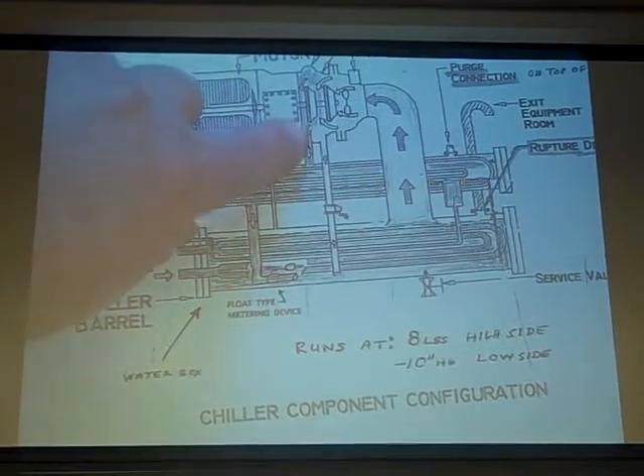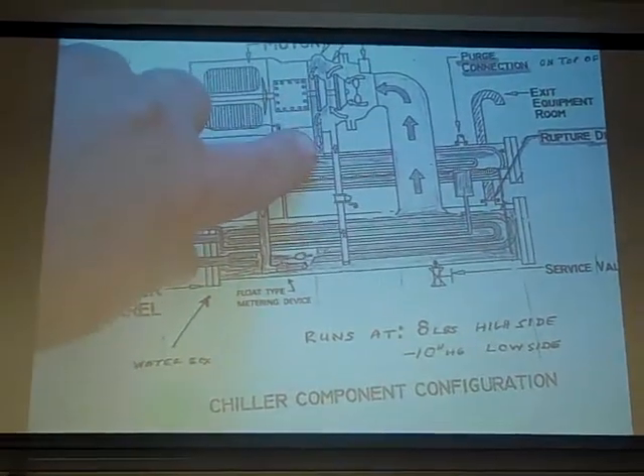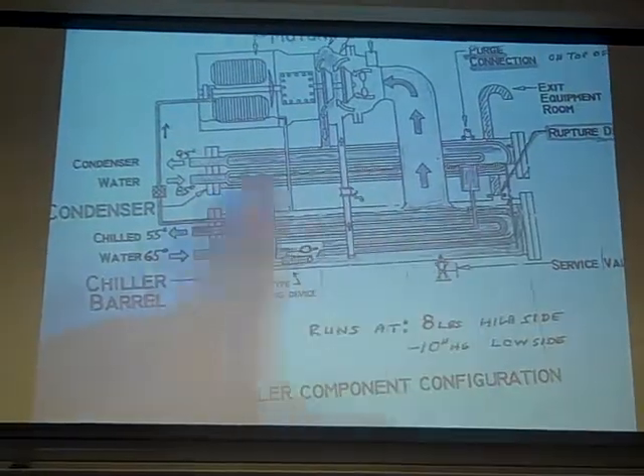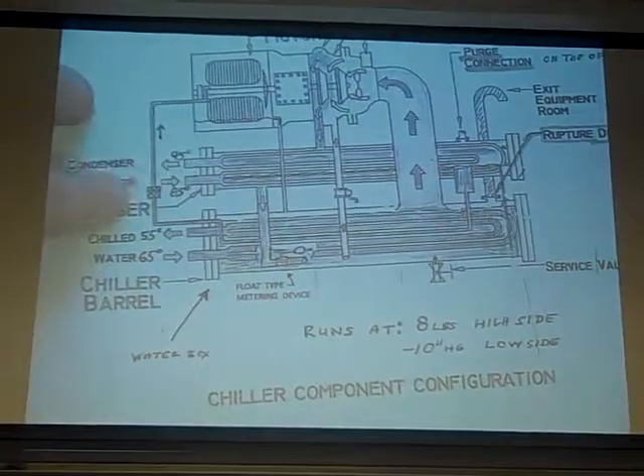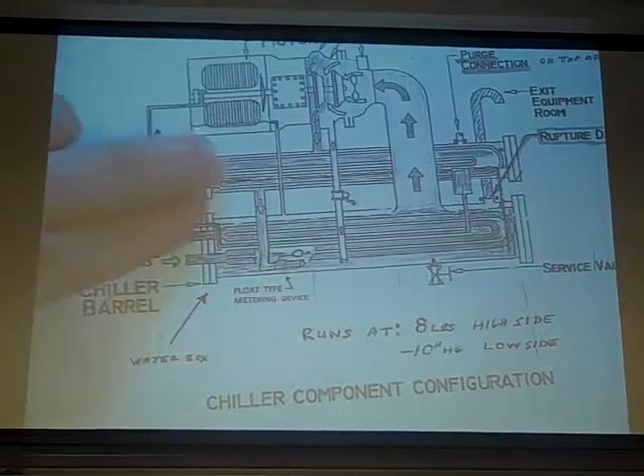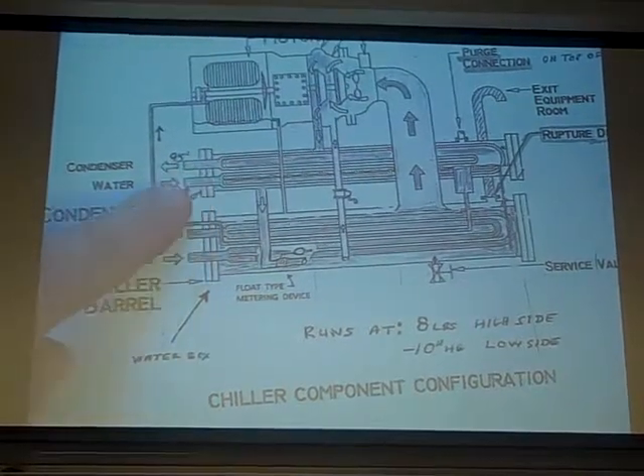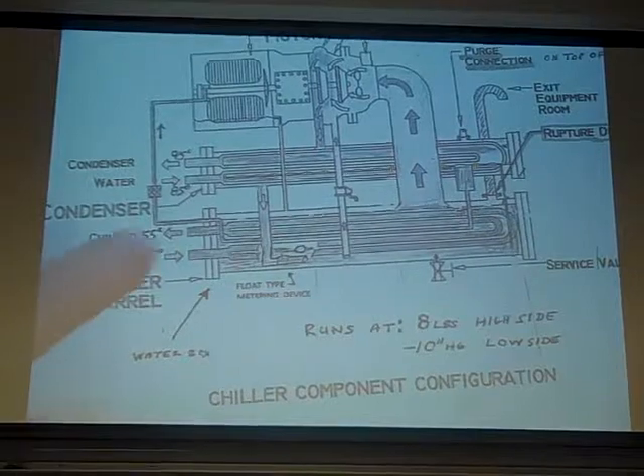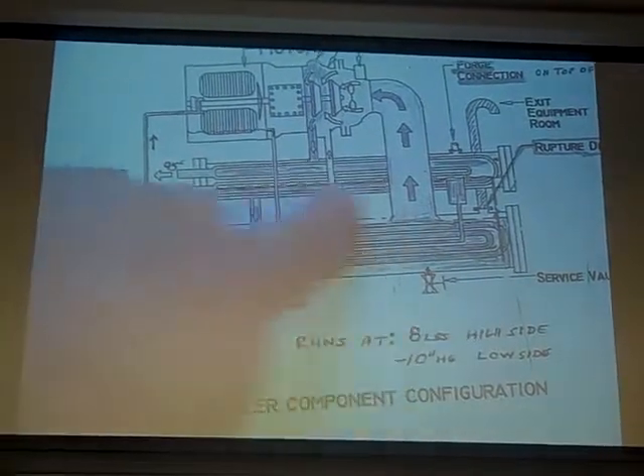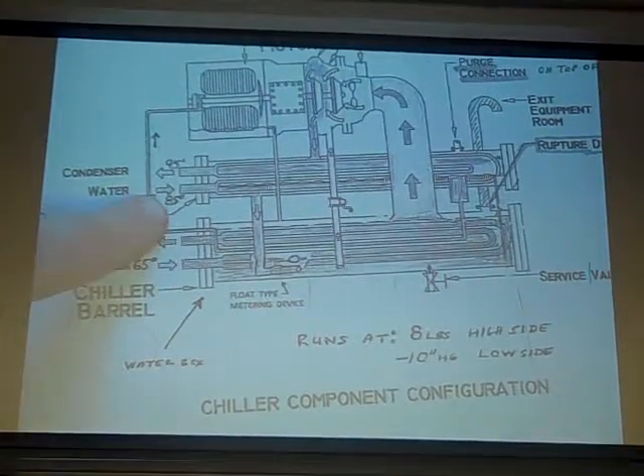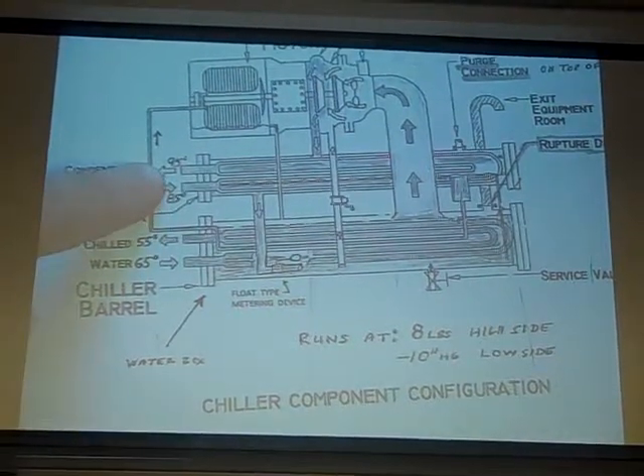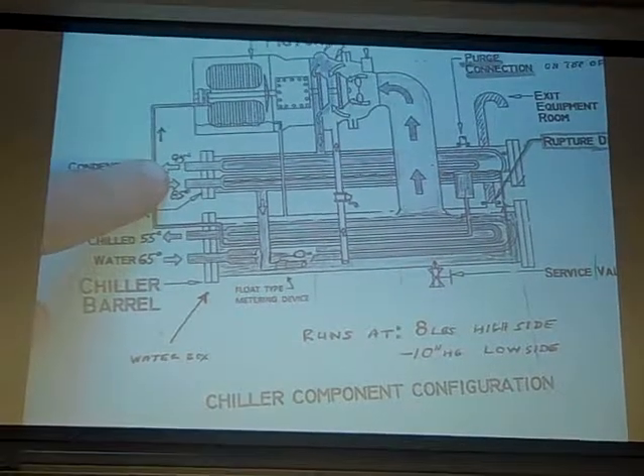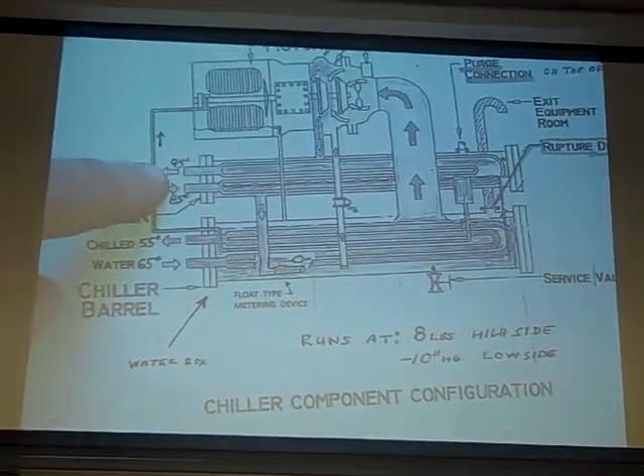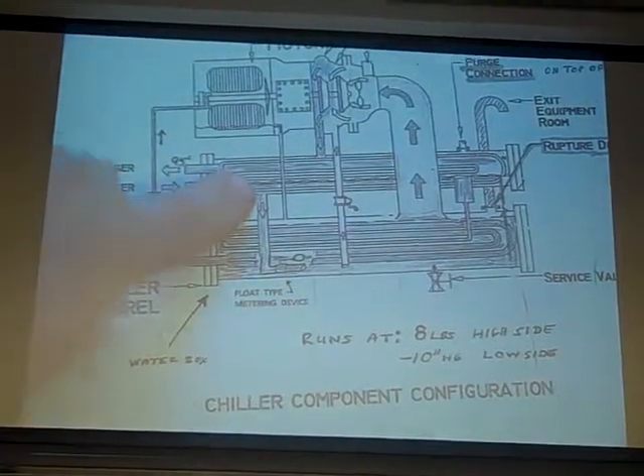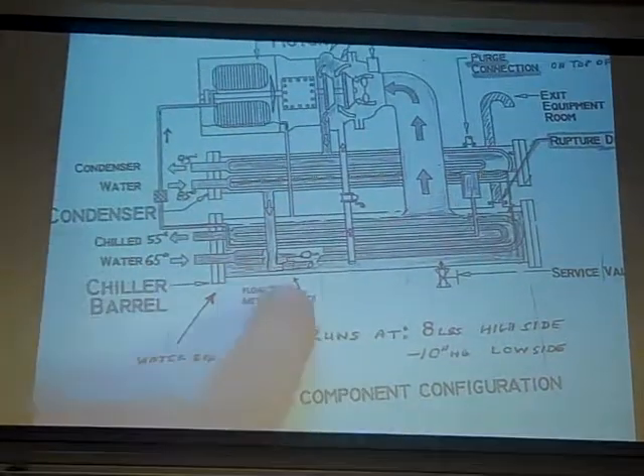When it takes them, it pushes that liquid or that gas now down into the first part, which is your condenser. You can see your water coming in here, going through these two little tubes. But there's probably 100 or so of those tubes that's going through. Works its way up through there, comes back out here. Comes in at 85 degrees, comes back out at 95 degrees. You pick the heat up out of that refrigerant, condensed it basically to a liquid. From there, it then just drops down into here.